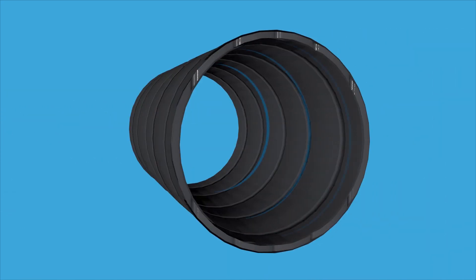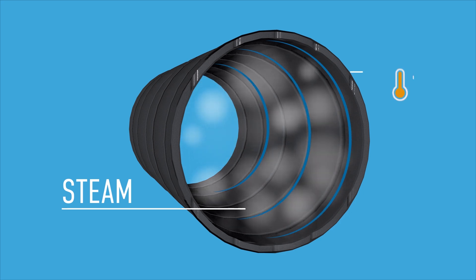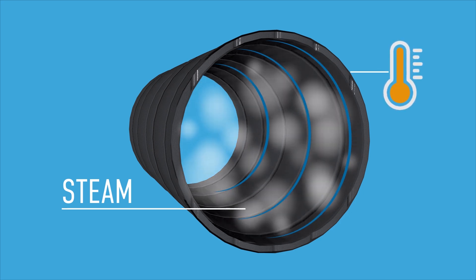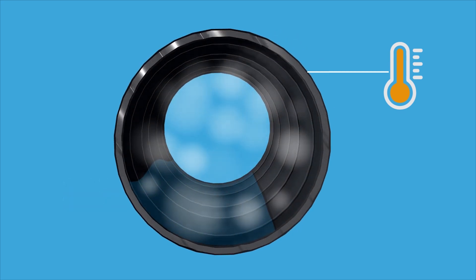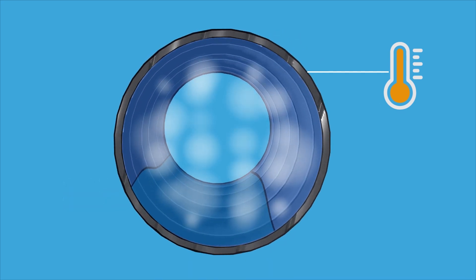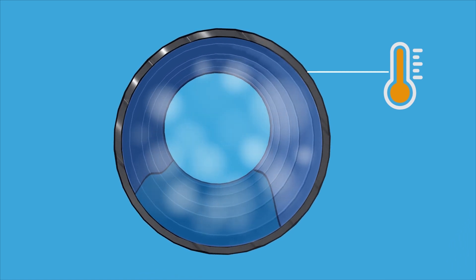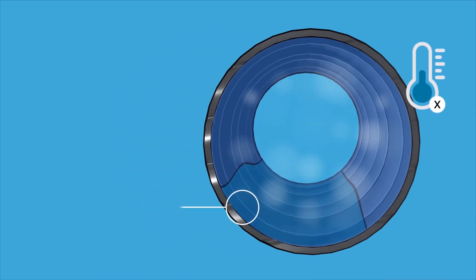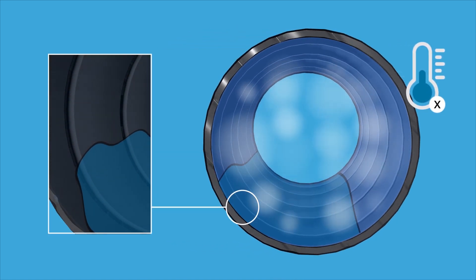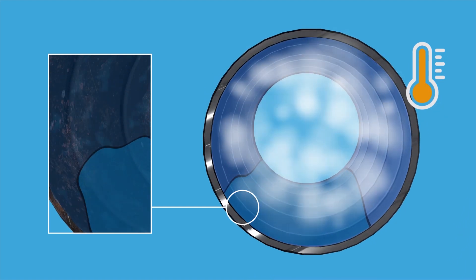Rotating cylinders are heated to remove residual moisture and, at the end, the paper only has from 2 to 9% of remaining water. When this operation takes place, a water film always forms due to the centrifugal forces, and even a very thin water film layer acts as an insulator and inhibits the heat transfer significantly. As a result, more steam is required to equilibrate temperatures.